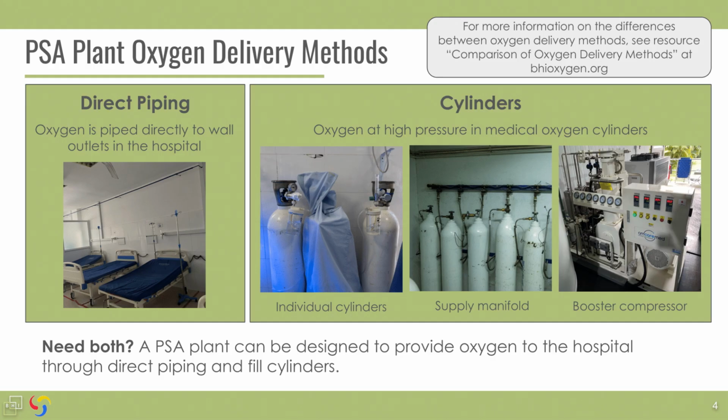Supply manifolds. Oxygen cylinders can deliver oxygen directly to patient bedsides by connecting to an oxygen pipeline. The arrangement of several oxygen cylinders to supply a pipeline is called a supply manifold.